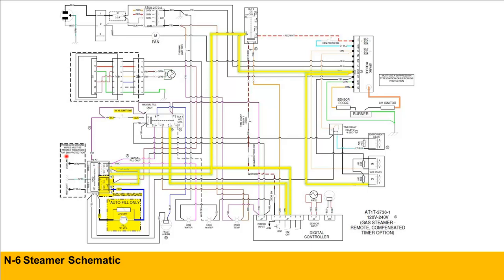Now, as Dan mentioned, once the lower water sensor sees water, it's going to go ahead and close this relay. Once this relay is closed, power will be transferred from the control board via the water board to the red wire, which will hit, as Dan mentioned, our DC relay, hit our module, and also hit our pilot valve. So at this point, what we'll do is remove the red wire off the water board, and once again, this is an output, so we're going to be testing the pin to ground. At this point, if we have 24 volts AC, the water board is okay.